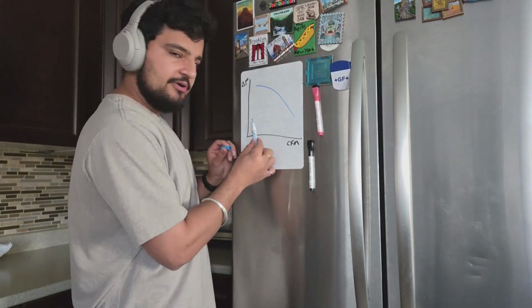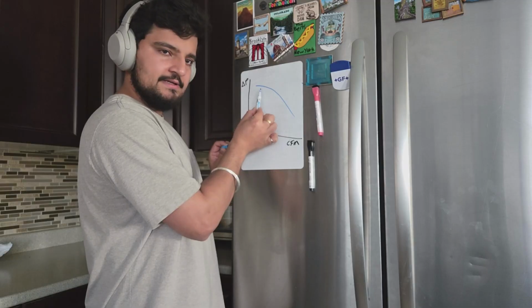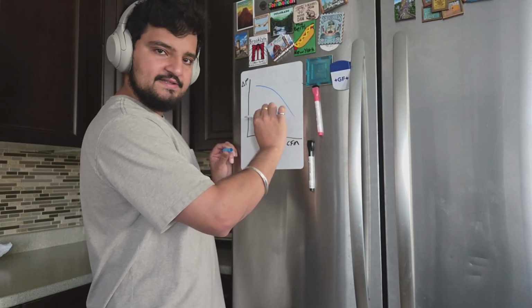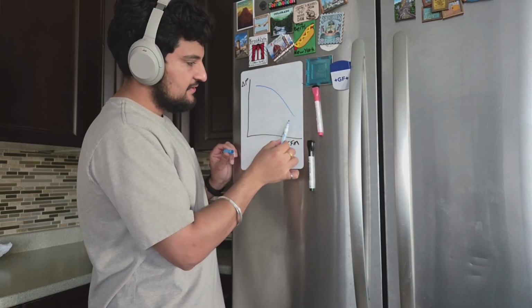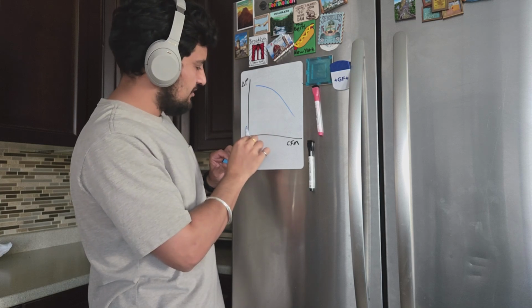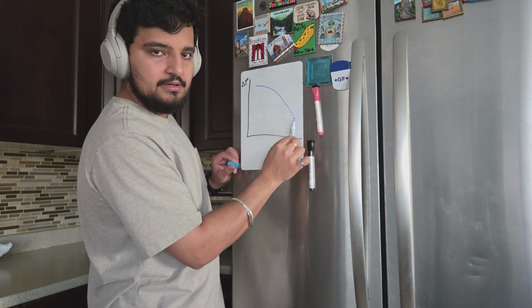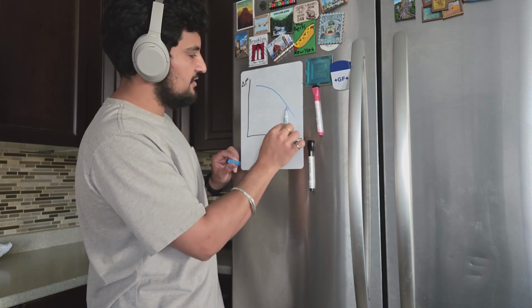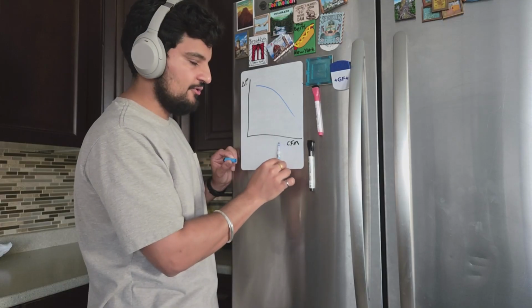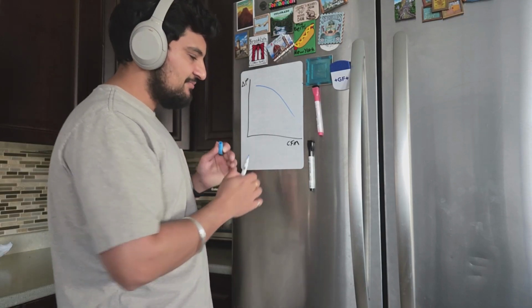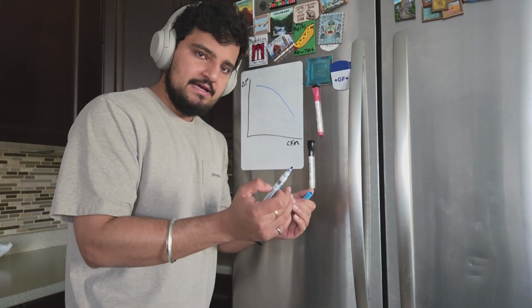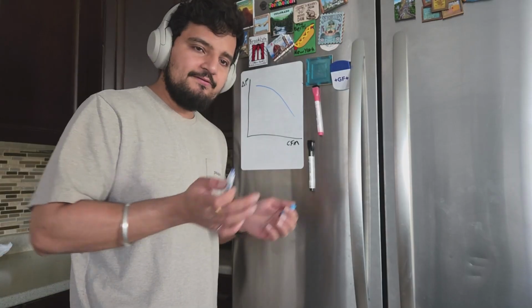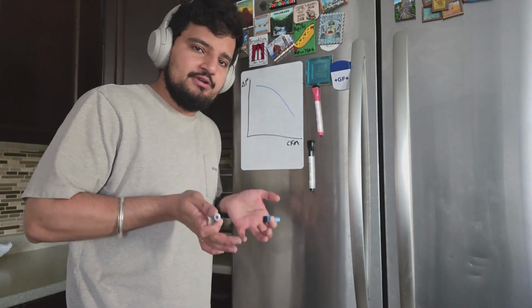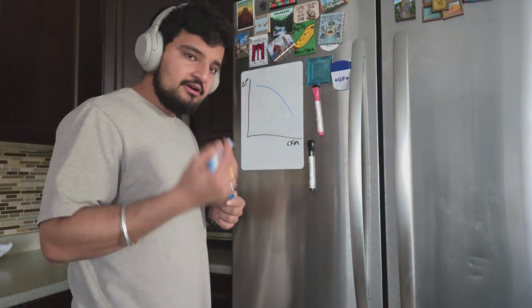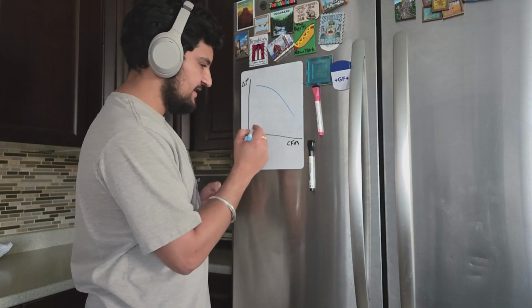The higher the pressure the fan has to fight against, the lower the flow gets, right? So let's say the pressure is very, very low, your flow is going to be very, very high. And as you start increasing the pressure, you're going to start decreasing the flow rate. So as the pressure the fan has to fight against increases, the flow that it's able to achieve at that pressure decreases. Now, on your ductwork, it goes something like this.